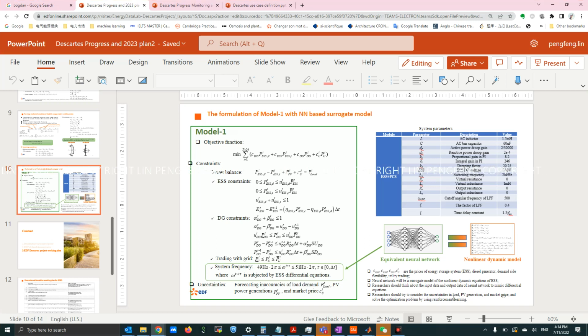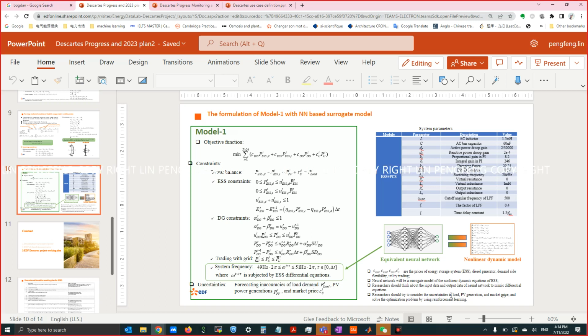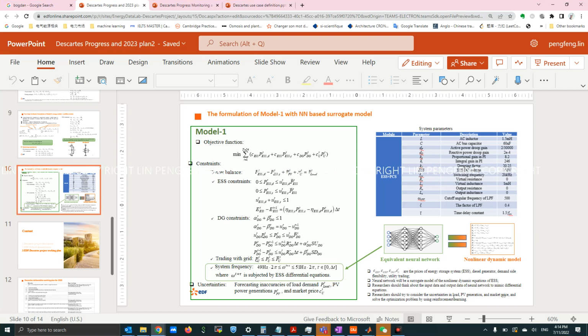The damping coefficient actually comes from the winding of the machines—that's where it comes from. Because of the winding and the inertia of the machines, that's what provides the damping coefficient. But if you don't have that—imagine you don't have the genset, imagine you only have the battery and the PV.